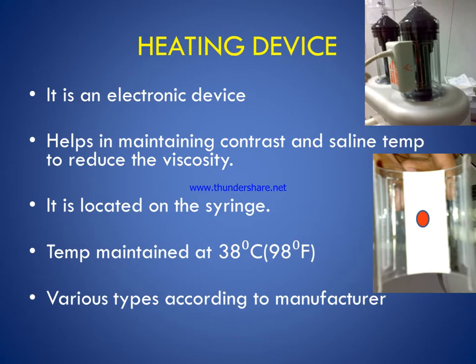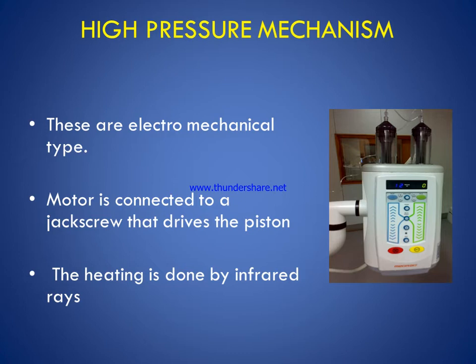The heating device is a thermostat device located behind the syringe. It is an electronic device which helps maintain contrast and saline temperature to reduce viscosity. It is located on the syringe and maintains a temperature of 38 degrees Celsius or 98 degrees Fahrenheit, varying according to the manufacturer. The high pressure mechanism is electromechanical: a motor is connected to a jack screw that drives the piston, and heating is done by infrared rays.